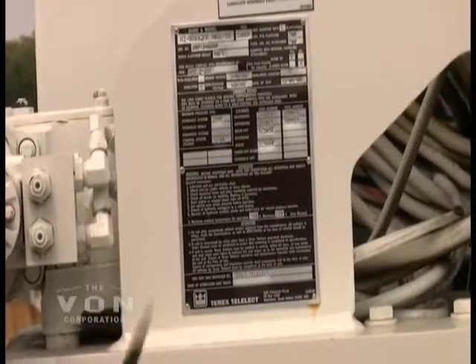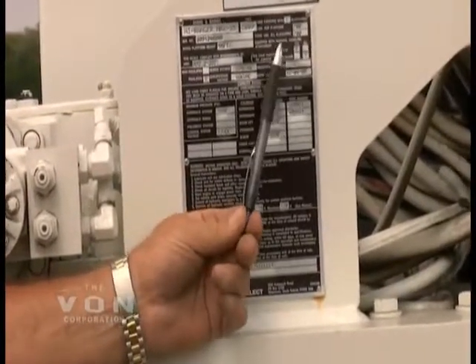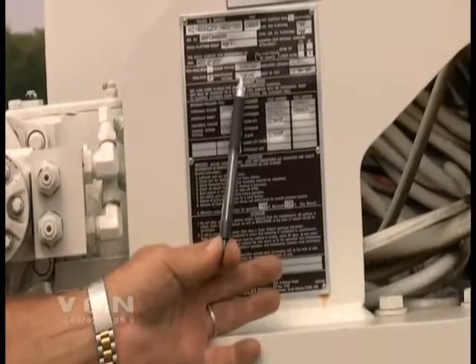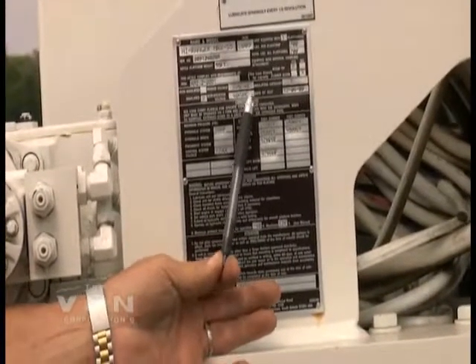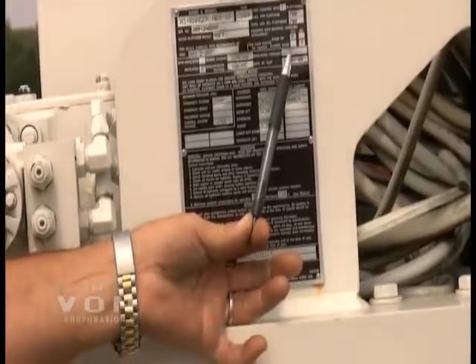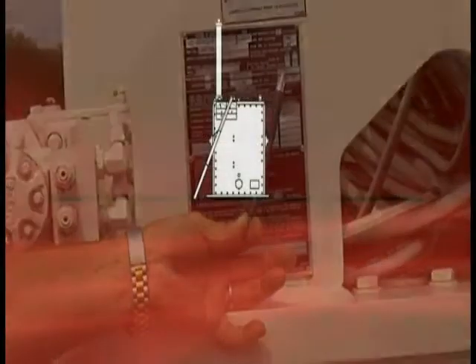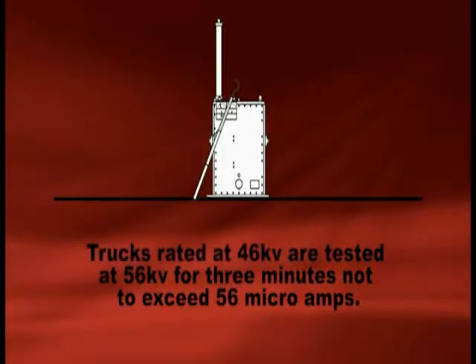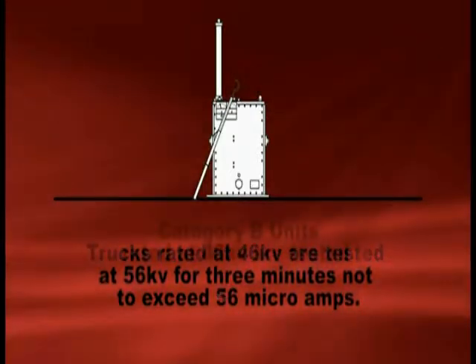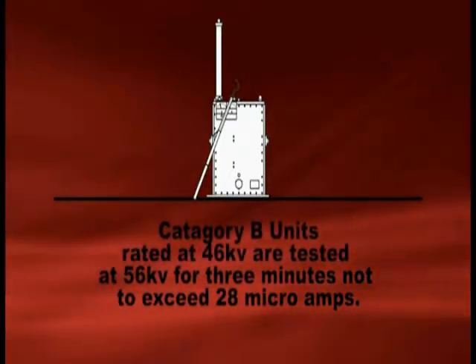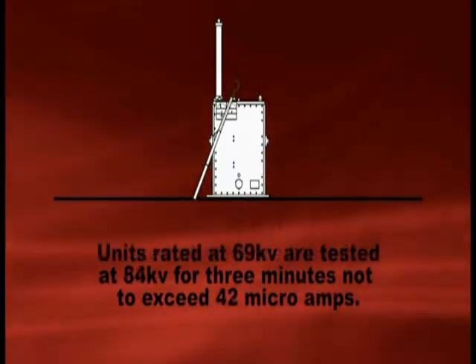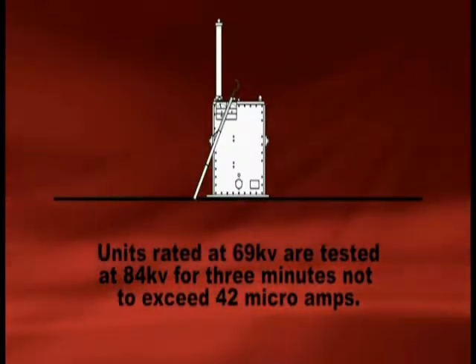What tells us how to test this is the qualification voltage, which is 46 kV AC, and its insulated category is C. Trucks rated at 46 kV are tested at 56 kV for 3 minutes, not to exceed 56 microamps. If they are category B units rated at 46 kV, they are tested at 56 kV, not to exceed 28 microamps. If they are rated at 69 kV, they are tested at 84 kV, not to exceed 42 microamps.